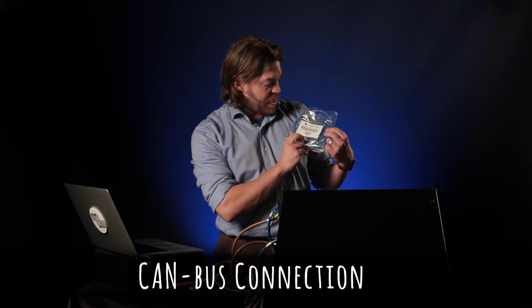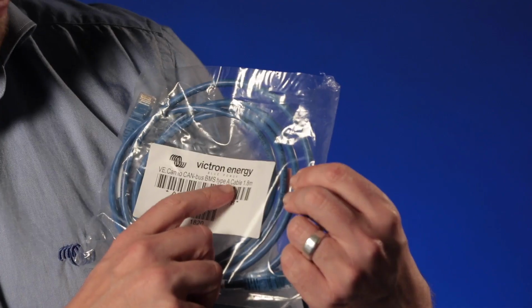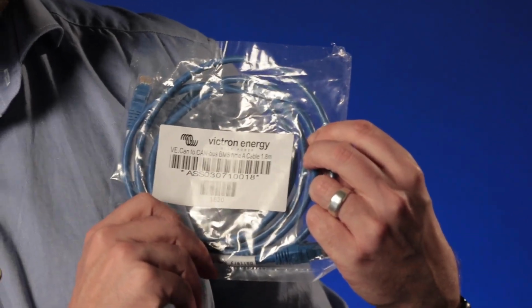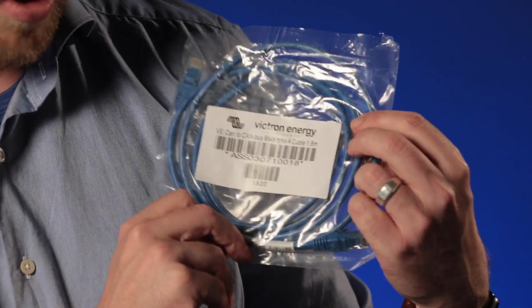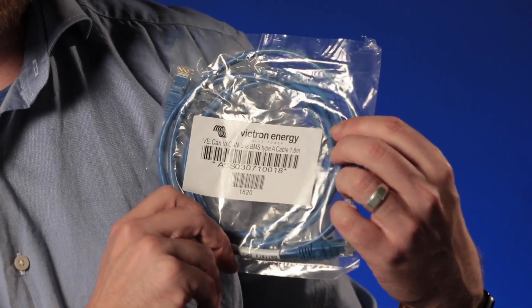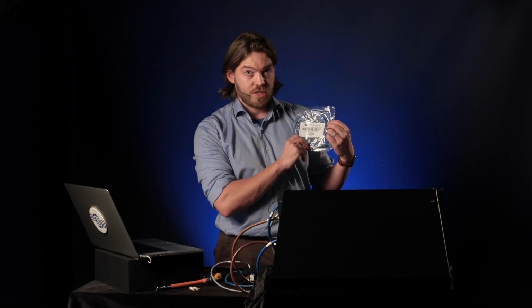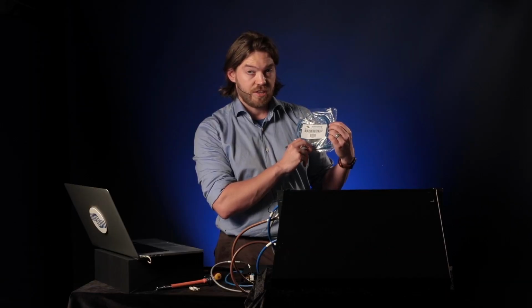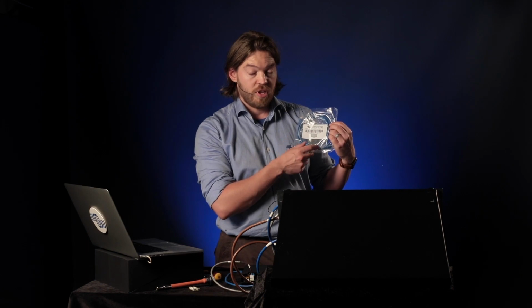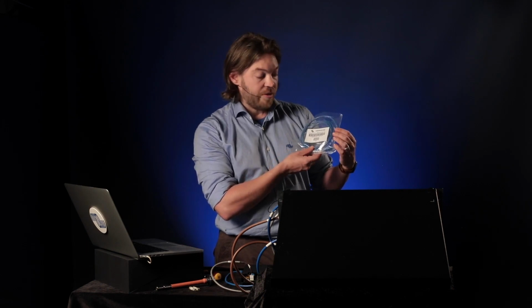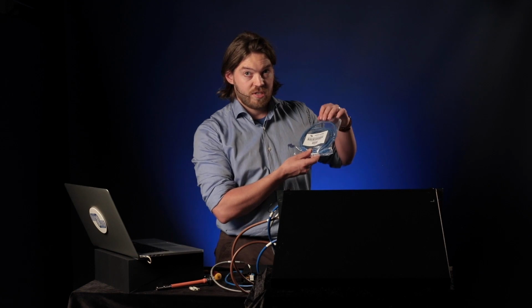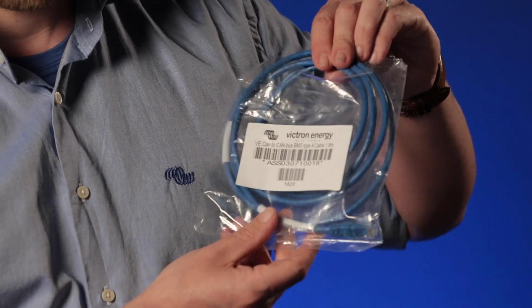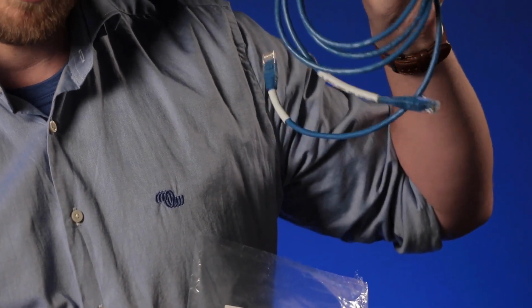The next communications cable connection we need to make is the special CAN bus type A cable. This VE CAN to CAN bus BMS type A cable is specific to BYD and Victron. You'll need to buy this cable from Victron, although we also supply the wiring guide - so if you want to make your own cable, for a longer length than what we provide, you can. But it's highly recommended to use a manufactured cable for this point. This is an essential communications cable and the system won't work properly without it.